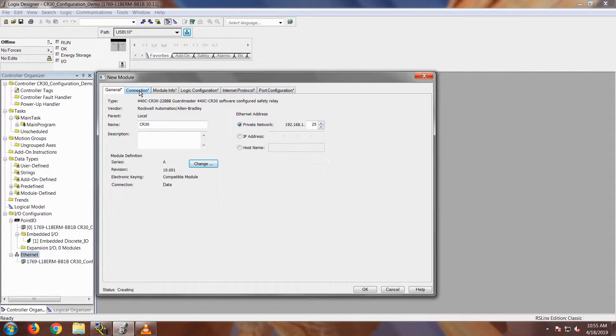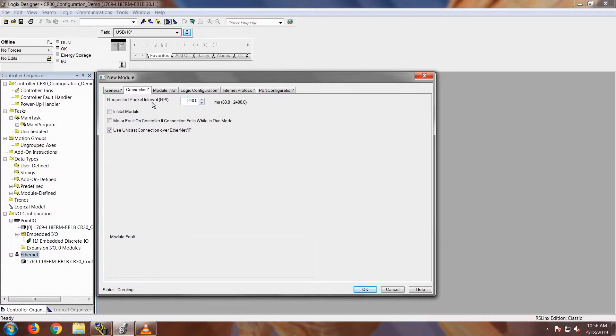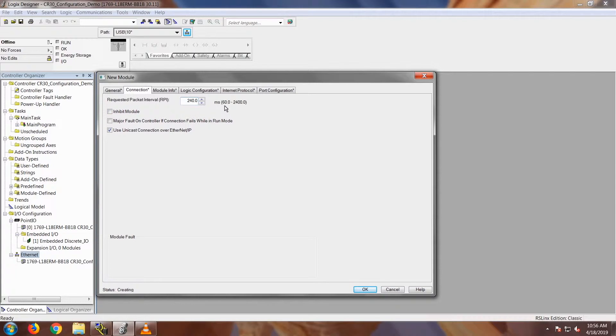Next we're going to go to the Connection tab, explore a little bit more about this add-on profile. Click on the Connection tab and you'll notice the requested packet interval, or RPI. It does default to 240 milliseconds, but you can change it anywhere from 60 to 2400 milliseconds, depending on how quickly you need to get the data.